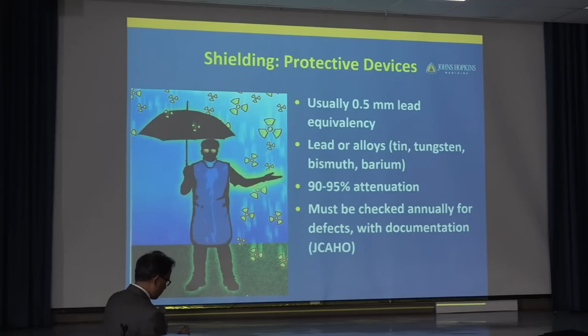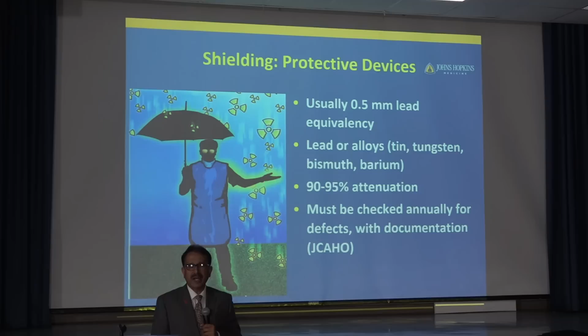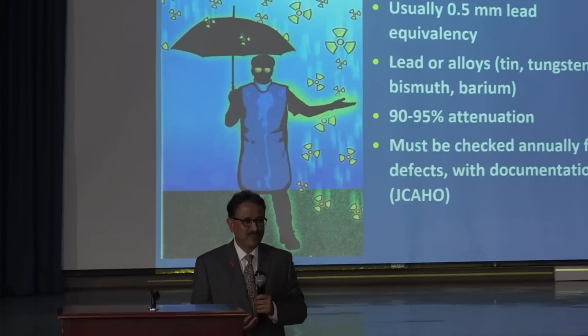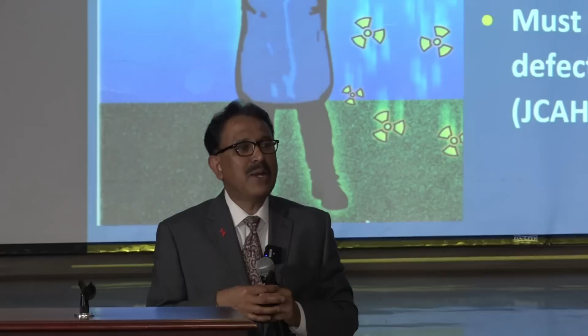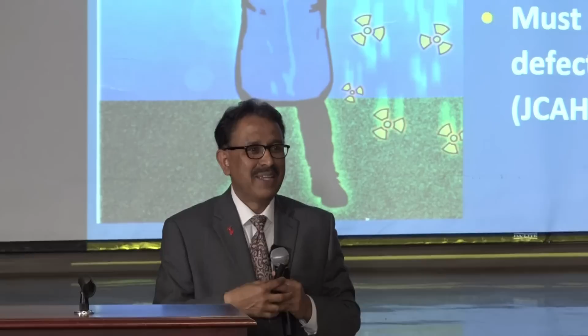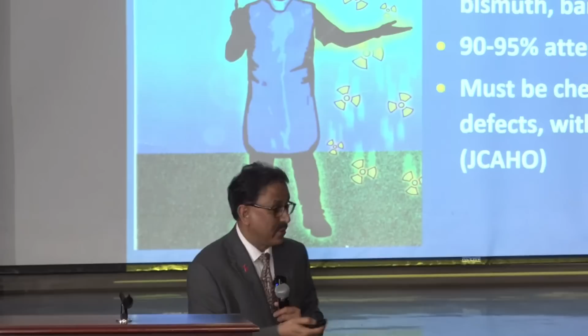Again, now the Joint Commission also requires documentation, so the technologist checks the aprons every year to make sure there is no gaping hole. It so happened one time, the fox watching the hen house. There was news that one manufacturer's aprons were radiating themselves, because they had picked up some materials somewhere else, and those materials had radioactive content. Because of that, these aprons were also radiating. So it was a big hue and cry. They had to take everything back. Anyway, so routine checking is very critical.